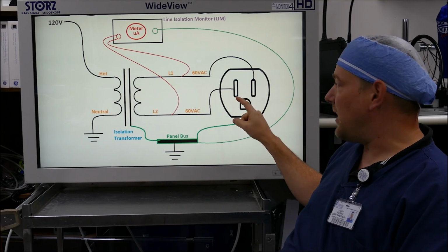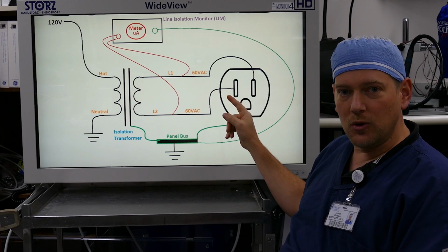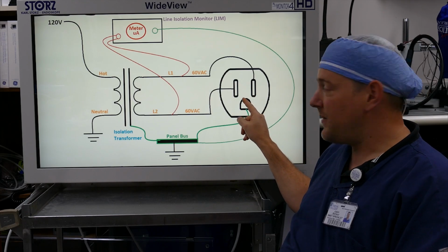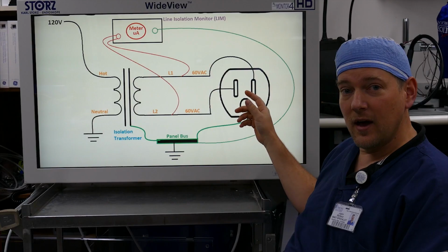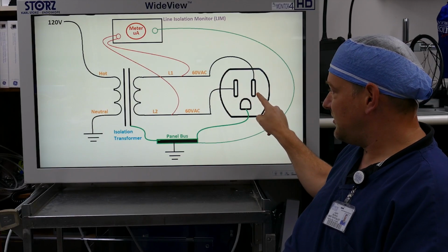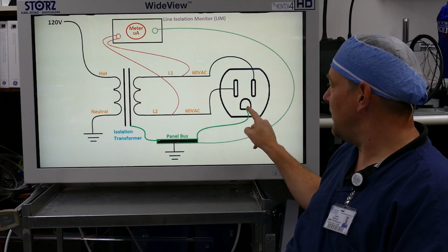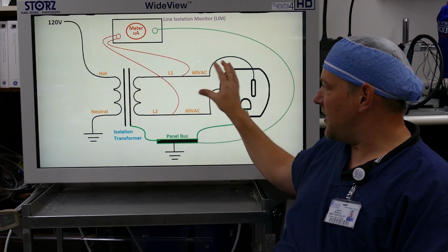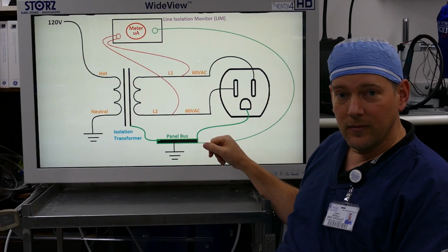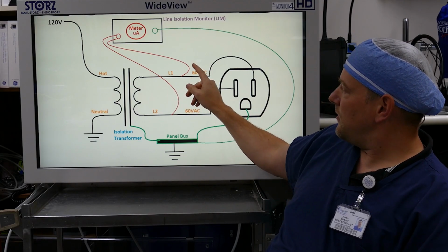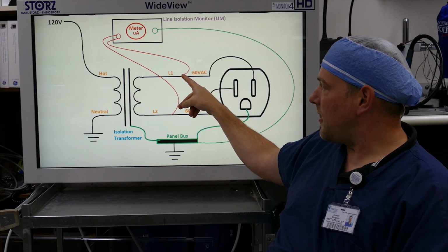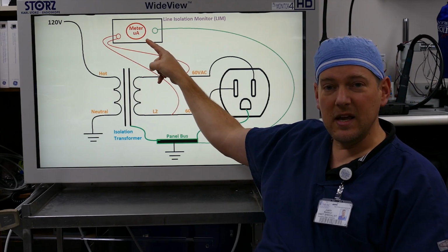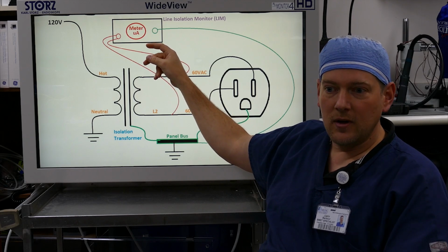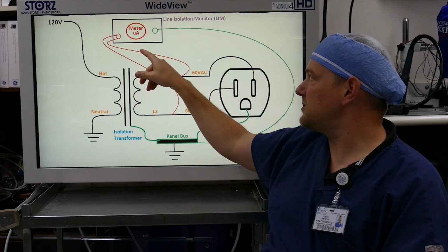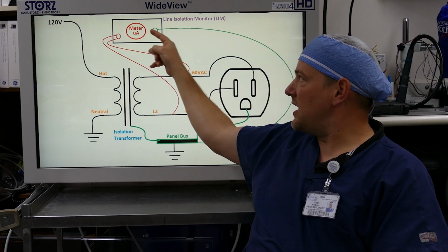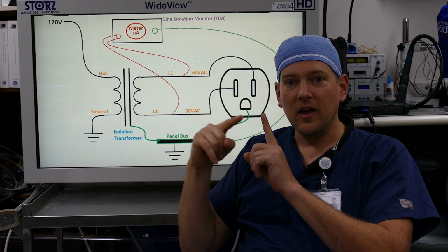So normally in an electrical outlet, you have a large opening, which would be your neutral. You have a small opening, which would be your hot, and then you have your ground. Well, in operating room electrical, you have 60 volts, and you have ground. Ground, if you can see here, has nothing to do with the other two. It's completely separate. So from L1 and L2, coming off the transformer, you have wires that go all the way up to your meter. And it's basically the same as a multimeter on microamps or milliamps. You have on one side L1 and L2, and on the other side ground. So between those two, it's measuring amperage.